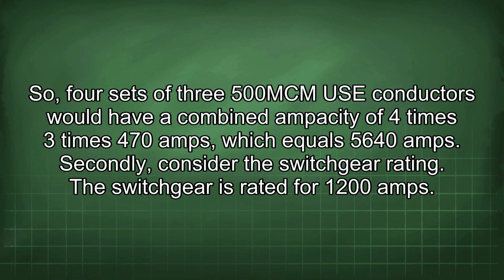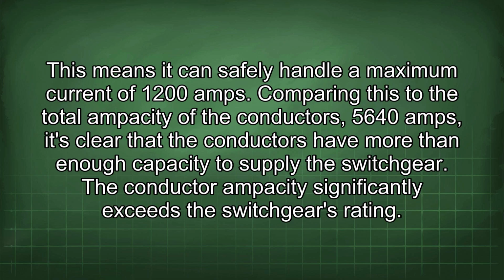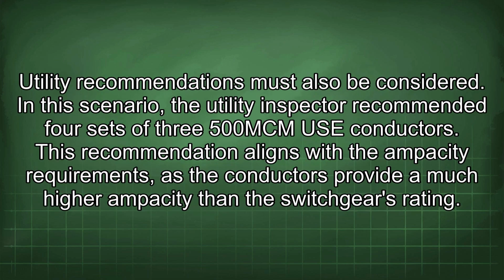The switchgear is rated for 1200 amps. This means it can safely handle a maximum current of 1200 amps. Comparing this to the total ampacity of the conductors, 5,640 amps, it's clear that the conductors have more than enough capacity to supply the switchgear. The conductor ampacity significantly exceeds the switchgear's rating. Utility recommendations must also be considered. In this scenario, the utility inspector recommended 4 sets of three 500 mcm conductors. This recommendation aligns with the ampacity requirements, as the conductors provide a much higher ampacity than the switchgear's rating.